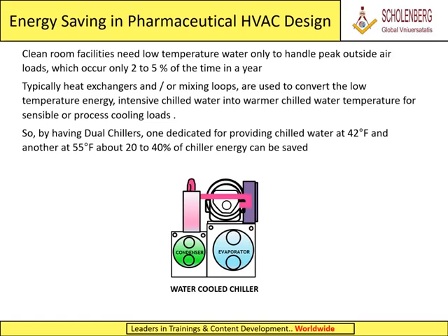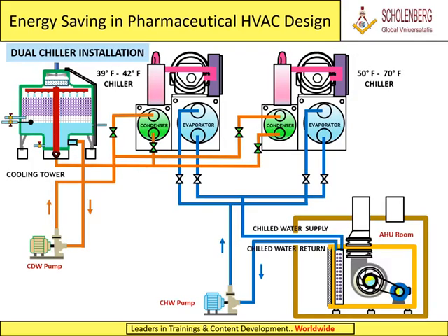Typically, heat exchangers and or mixing loops are used to convert the low temperature energy intensive chilled water into warmer chilled water temperature for sensible or process cooling loads. So, by having dual chillers, one dedicated for providing chilled water at 42 degrees Fahrenheit and another at 55 degrees Fahrenheit, about 20 to 40% of chiller energy can be saved. Dual chiller installation.